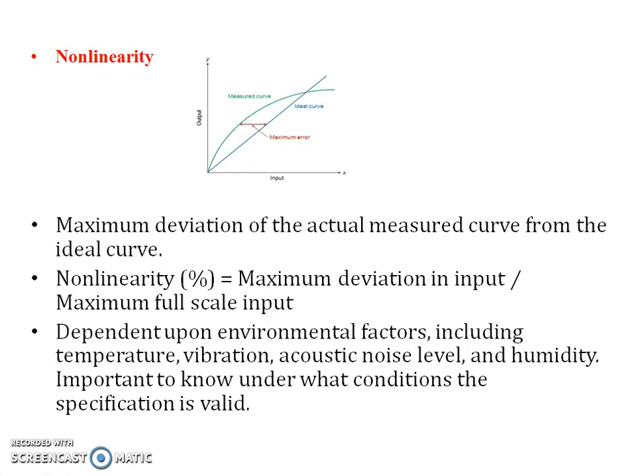Non-linearity is the maximum deviation of the actual measured curve from the ideal curve. It is equal to the maximum deviation in input divided by the maximum full-scale input. It depends upon environmental factors including temperature, vibration, acoustic noise level, and humidity. It is important to know under what conditions this specification is valid.